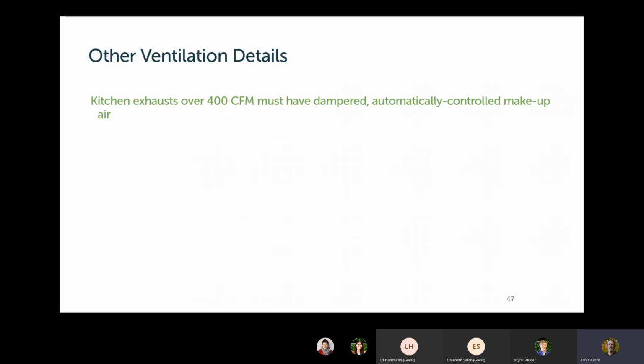If you have a huge kitchen exhaust, you've got to have makeup air. Over 400 CFM is a lot of exhaust. This does not apply to your standard exhaust hood in your standard house. But there are some, especially upper end houses, that have almost commercial restaurant style cooking equipment. And sometimes they will have rather large vent hoods that move an awful lot of air. And what the code says is if your exhaust moves over 400, then you have to have a dampered, automatically controlled makeup air unit.